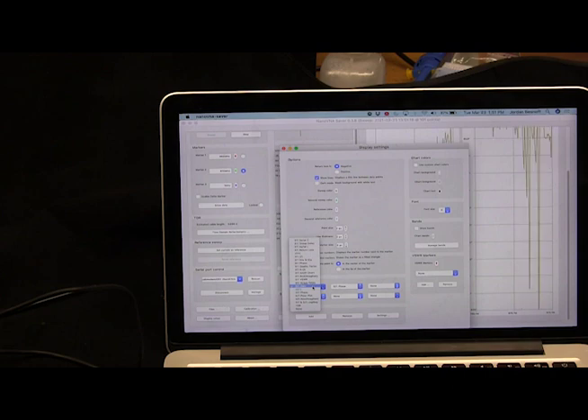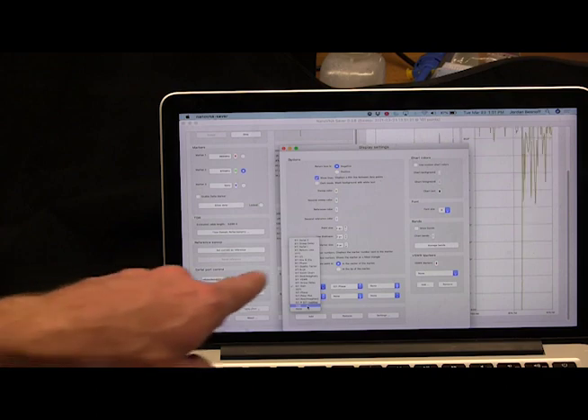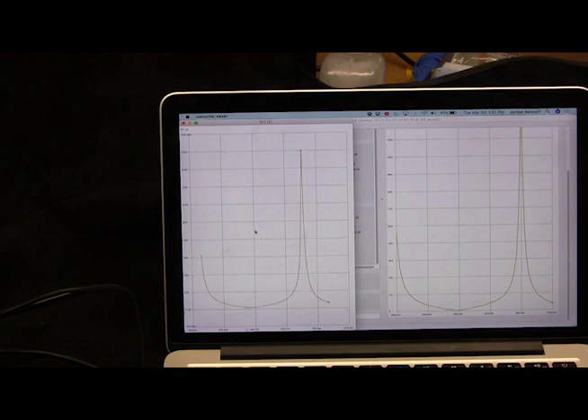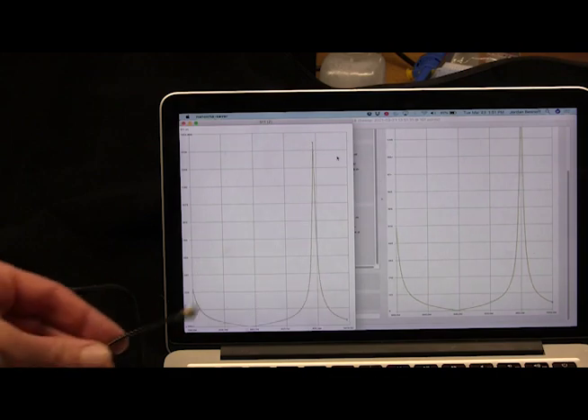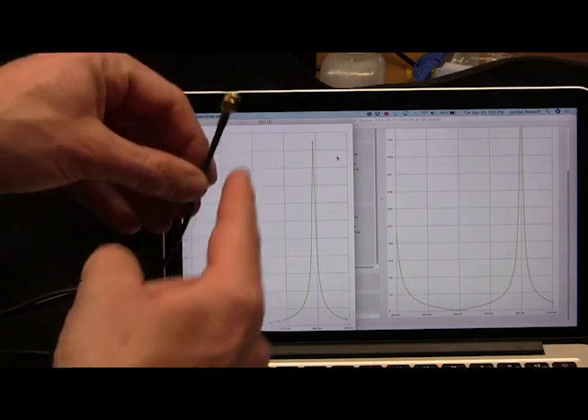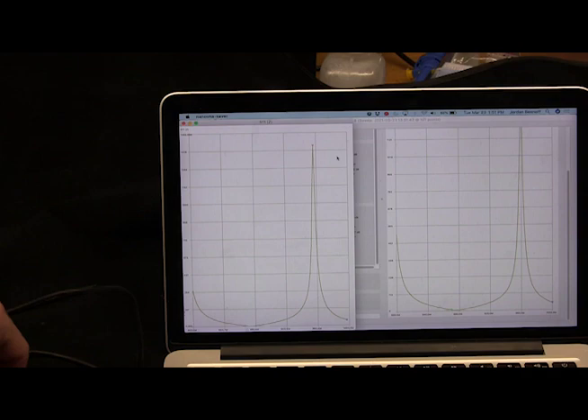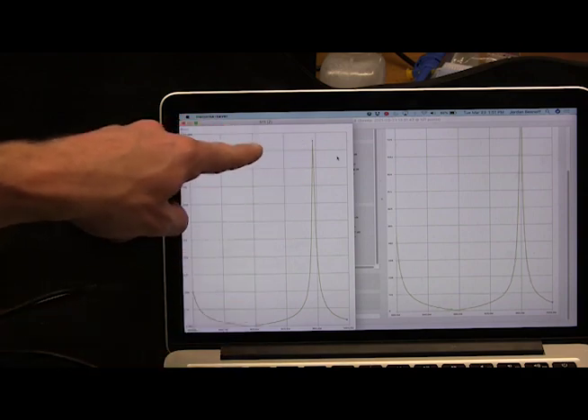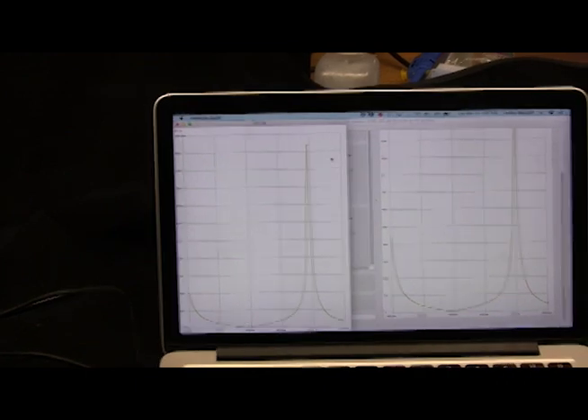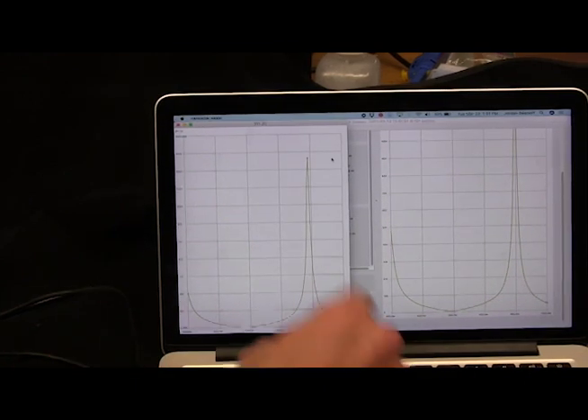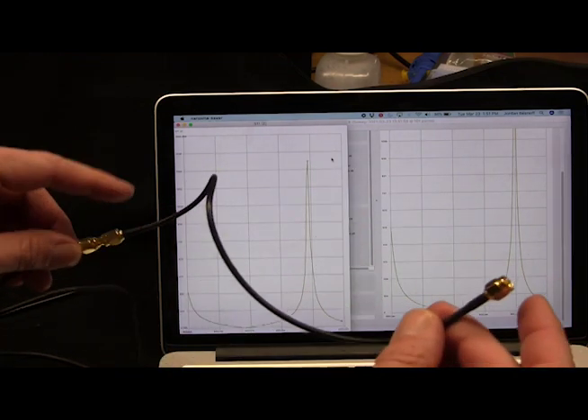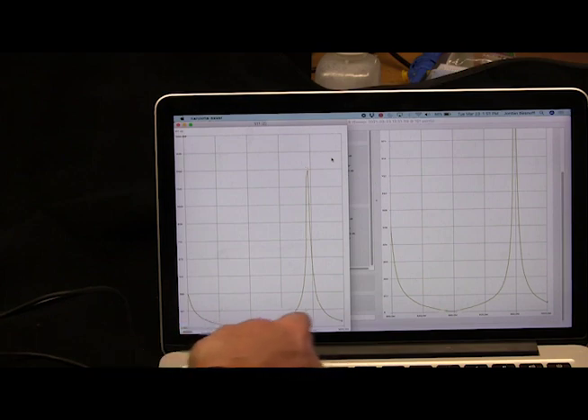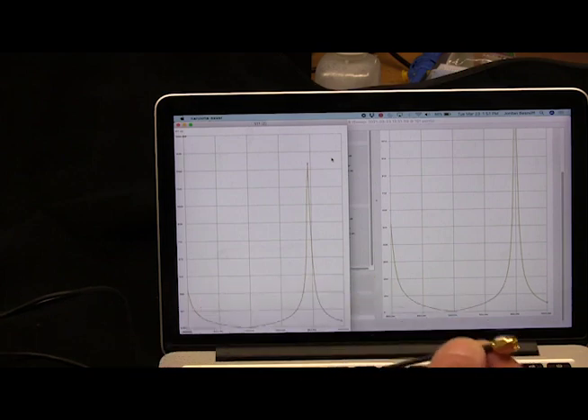Now we're going to change our setting to S11 Z, and we're going to get rid of the S21 phase. And what you'll see here is that we have a peak. What's happening is our device under test is an open here, but for every quarter wavelength, that open is going to become a short. So here, it is a low impedance. Here, it's a high impedance. So at the low impedance, we have this open being a short, and at the high impedance, we have the open being an open. What that means is the frequency difference between those two is the difference in frequency for this being a quarter wavelength.